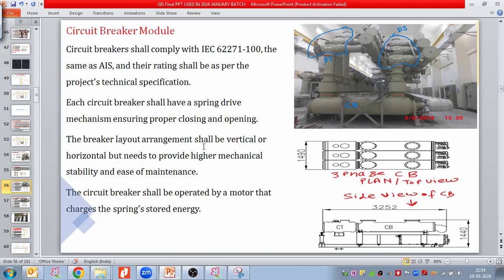The breaker layout arrangement shall be vertical or horizontal. Generally, for 66 kV, 110 kV, 132 kV, we can go with the vertical arrangement. But for 220 kV, 400 kV, 765 kV, we go with the horizontal arrangement. In this particular site photo, the breaker is in a horizontal arrangement, which provides higher mechanical stability and ease of maintenance. The breaker shall be operated by a motor that charges the spring stored energy.